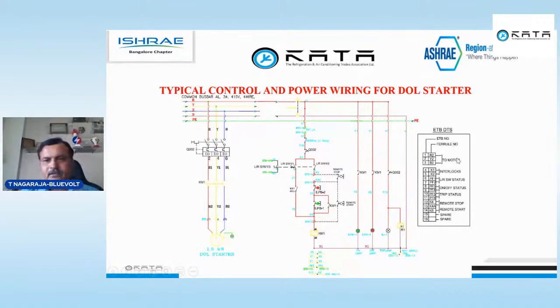These are all the interlocks we have given. For two motors, we have given interlocks K1, K2. That means your door interlock, limit switch, all the interlocks are given. Then the status to the BMS, trip status to the BMS, and remote start stop command are also given. This remote start stop will generally be there in all panels because of authority norms. Once the motor is beyond 10 meters from the panel, or the panel is not visible, we have to connect these remote start stop push buttons.